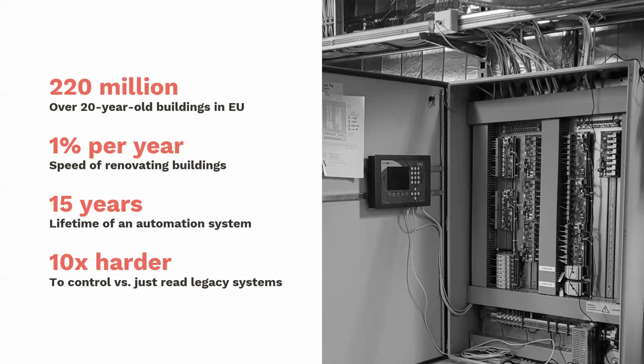You have these I/O modules essentially reading data from things like sensors in air ducts and so on. The data is fed into a CPU, which has internal set points or a desired state for the building's processes, makes adjustment calculations, and sends data back into the I/O modules, which drive things like fans and valves.